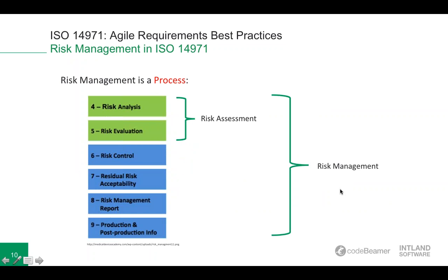Now, risk management, according to the aforementioned ISO 14971, is defined in 2 parts: the probability of occurrence of harm and the consequences of that harm, or how severe it might be, in other words. In this case, a medical device company has to consider this definition and then expand on a given product's risk by using tools such as the risk analysis, risk evaluation, risk control, and production and post-production information throughout the initial development to product realization and eventual delivery of your product.